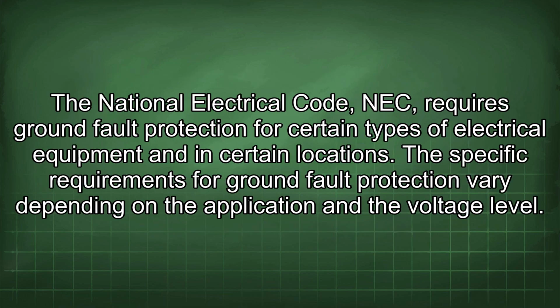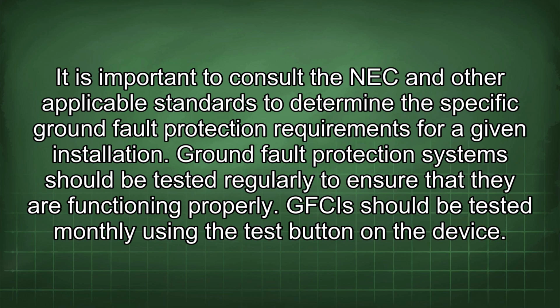Ground fault relays are commonly used in industrial and commercial facilities to protect motors, transformers, and other electrical equipment. The National Electrical Code, NEC, requires ground fault protection for certain types of electrical equipment and in certain locations. The specific requirements for ground fault protection vary depending on the application and the voltage level. It is important to consult the NEC and other applicable standards to determine the specific ground fault protection requirements for a given installation.